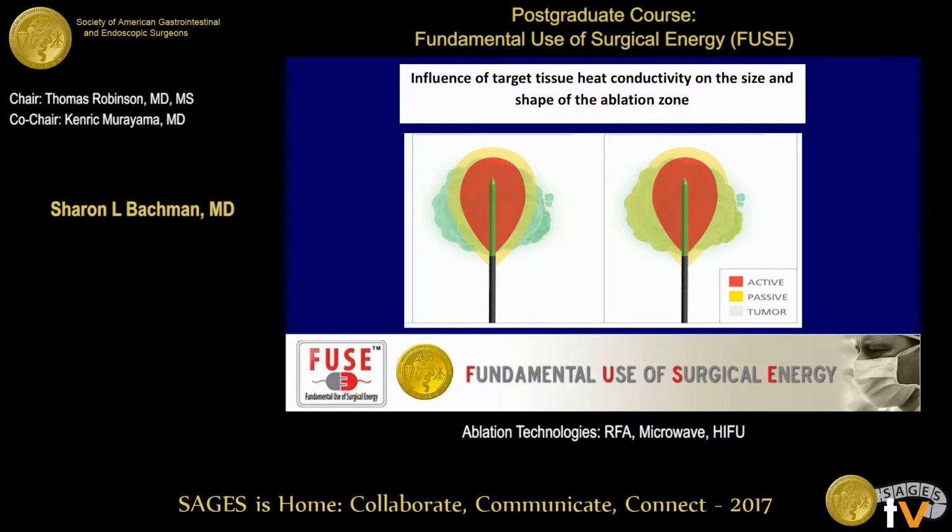And depending on how much conductivity your tissue has, so if there's a lot of water in it, obviously you will have your current go farther, right? So it will propagate through the tissues more. Just like with monopolar energy, as you change the tissue, as it desiccates and you get your effect, the impedance goes up in the tissue and you are less able to transmit the current through it. So you have to keep the kind of tissue you have in mind when you're using these devices. Obviously, something with a higher water content is going to be more effective. But as your effect goes on, the device itself will be less effective.